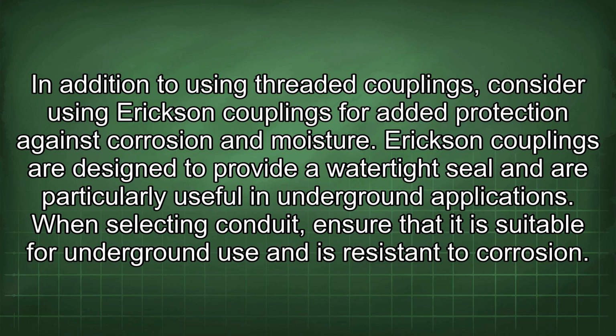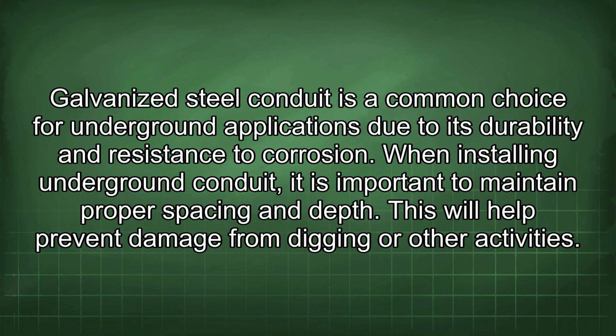In addition to using threaded couplings, consider using Erickson couplings for added protection against corrosion and moisture. Erickson couplings are designed to provide a watertight seal and are particularly useful in underground applications. When selecting conduit, ensure that it is suitable for underground use and is resistant to corrosion. Galvanized steel conduit is a common choice for underground applications due to its durability and resistance to corrosion.